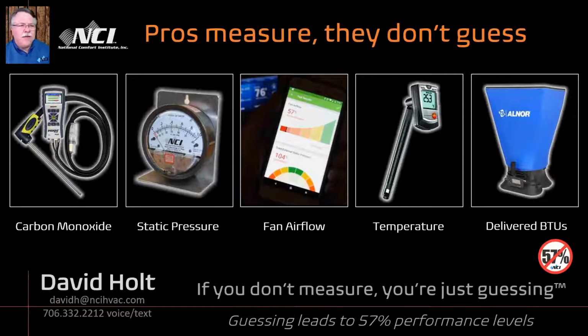Now, some of you are thinking, with these new ECM motors, we just dial up what we need. I can get on my thermostat or my cell phone for some manufacturers and dial in what CFM I need, and not worry about it. Well, I've done testing on some of those cool systems, dialed in what CFM I needed, then started restricting the airflow using an airflow simulator. And guess what we figured out? Yeah, it'll run. That fan will run.